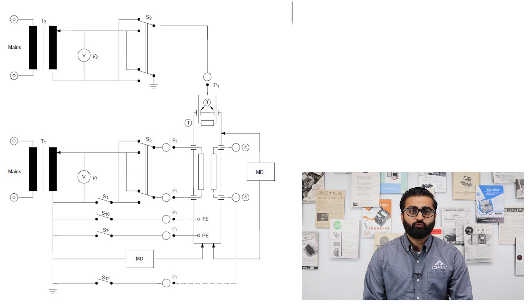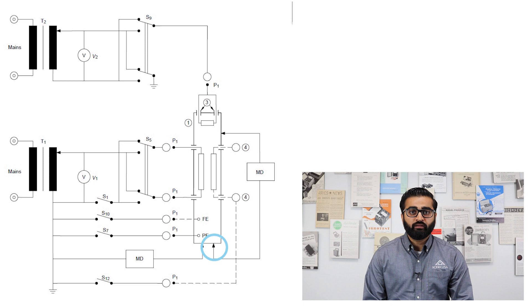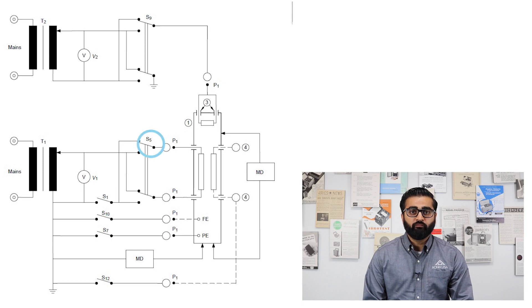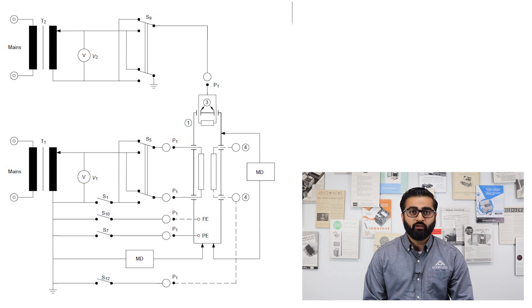Now let's review figure 14 from the IEC 60601 standard. This image represents the circuit model for measuring touch current. On one side of the MD, it comes in contact with an enclosure point. The other side of the MD comes in contact with the low side or reference earth. We could also see another MD placed between two enclosure points. We have switches S1 open neutral, S5 reverse polarity, and S7 open ground. These switches are used to simulate fault conditions within the device. In our second part of the video, we'll be using S7 to simulate an open ground and closed ground situation within the medical device.